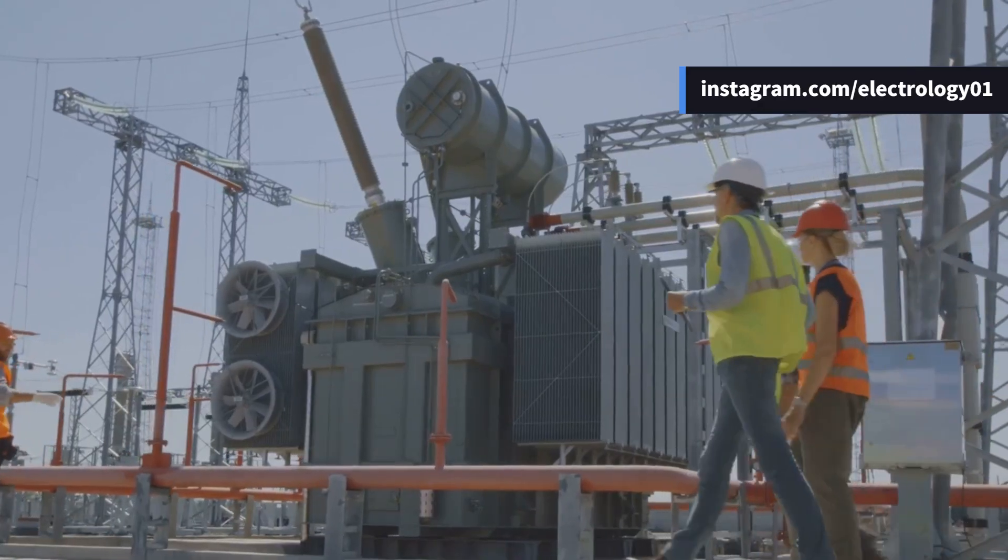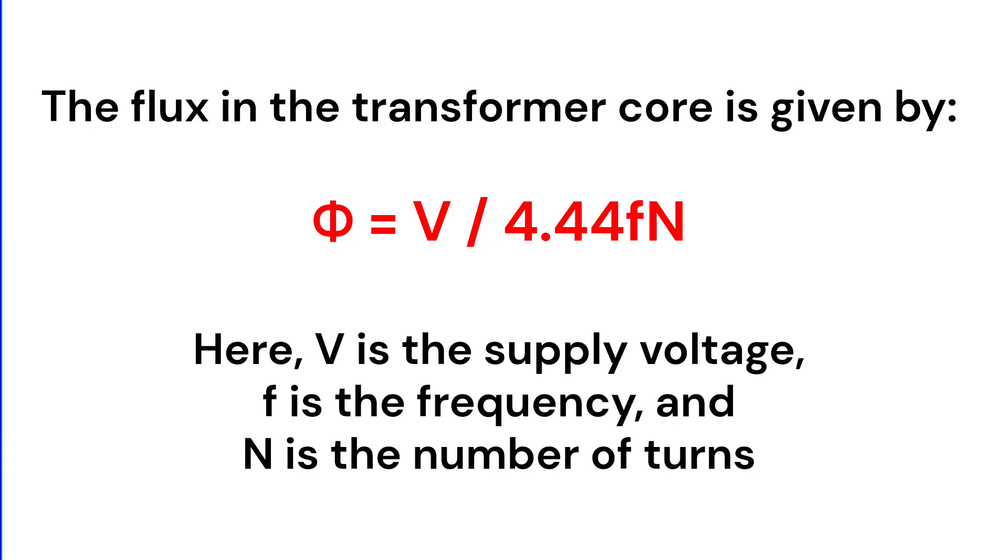Now, let's break it down mathematically. The flux in the transformer core is given by the formula phi equals V by 4.44FN. Here, V is the supply voltage, F is the frequency, and N is the number of turns. Assuming the number of turns is constant, the flux is directly proportional to the V/F ratio. This means if the voltage increases or the frequency decreases, the flux in the core will rise.